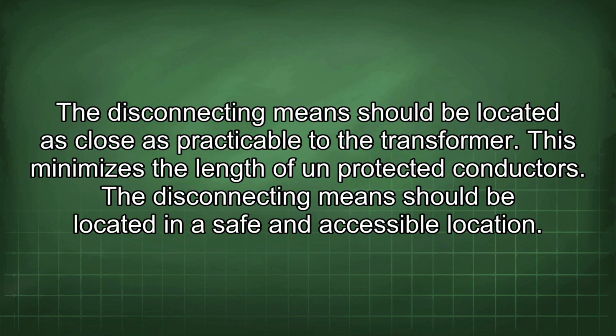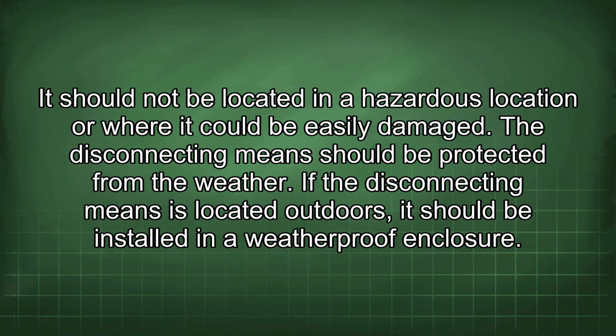The disconnecting means should be located as close as practicable to the transformer. This minimizes the length of unprotected conductors. The disconnecting means should be located in a safe and accessible location. It should not be located in a hazardous location or where it could be easily damaged. The disconnecting means should be protected from the weather. If the disconnecting means is located outdoors, it should be installed in a weatherproof enclosure.